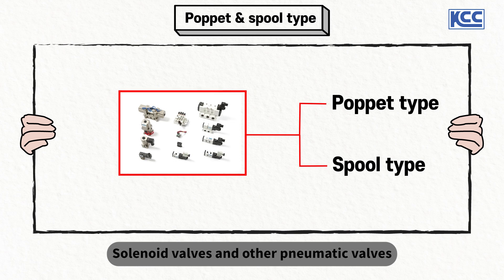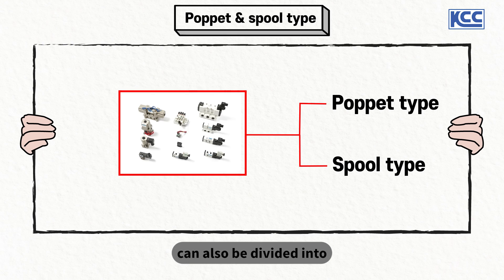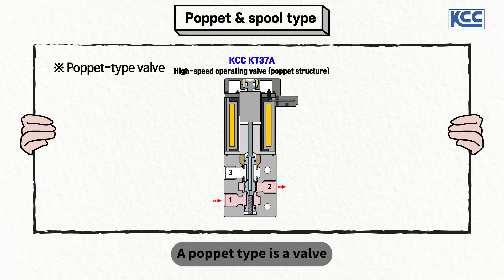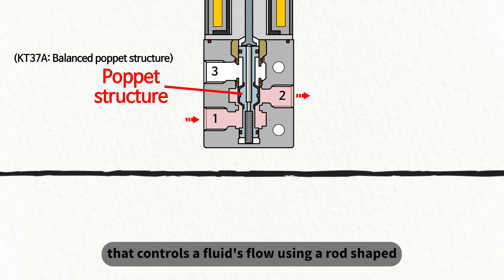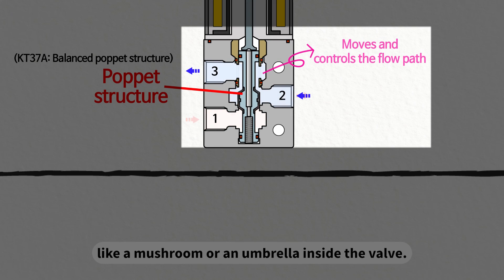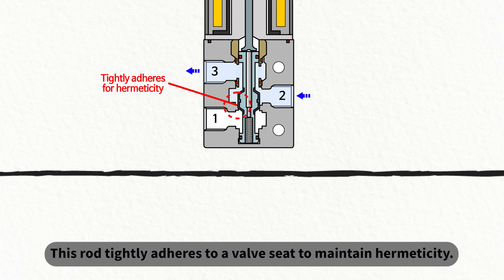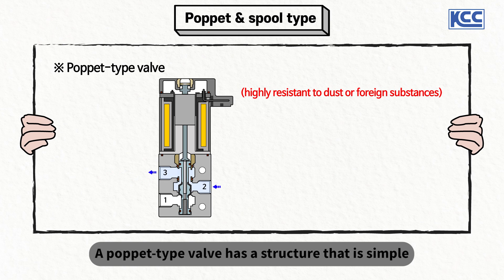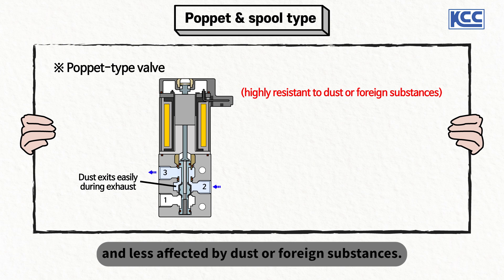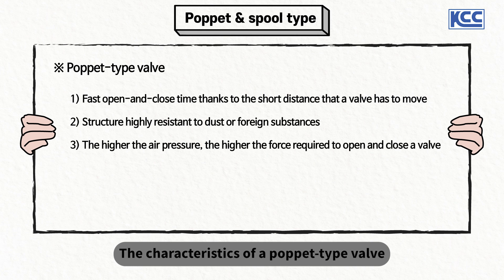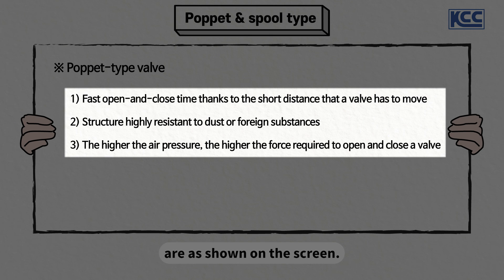Solenoid valves and other pneumatic valves can also be divided into poppet type and spool type depending on the structure. A poppet type is a valve that controls a fluid's flow using a rod shaped like a mushroom or an umbrella inside the valve. This rod tightly adheres to a valve's seat to maintain hermeticity. A poppet type valve has a structure that is simple and less affected by dust or foreign substances.